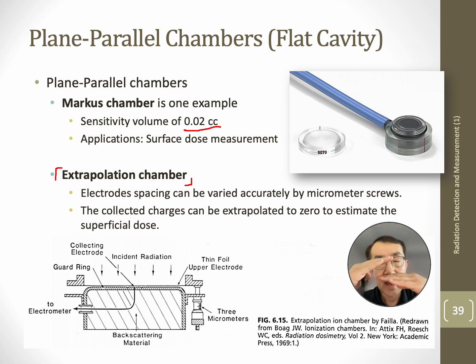In this special parallel plane chamber, you can adjust the separation of that thin active volume. Those two electrodes can be adjusted in very fine resolution.